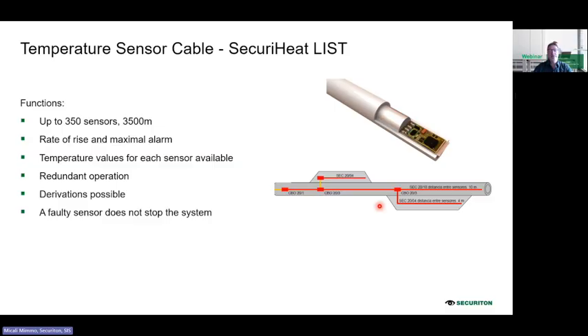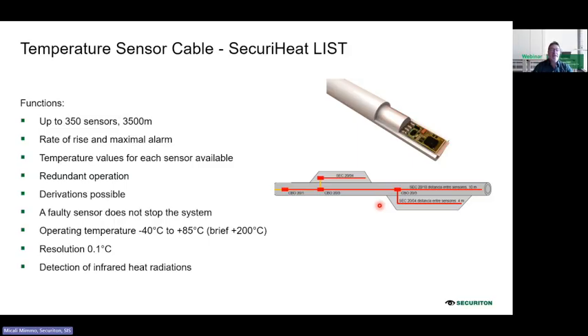This is also important to know: there is always coverage by the fire detection system, even if we have a faulty sensor. Then we also have, as mentioned before, the operating temperature. It may reach 200 degrees. This is not a problem for the cable. Of course, if it increases to 200, 300, 400 degrees, there will be some damage to the cable, but then we already have a fire in the tunnel, and a lot of equipment must be exchanged when we have such high temperatures.